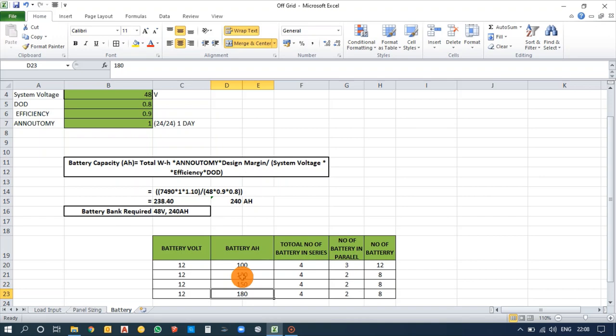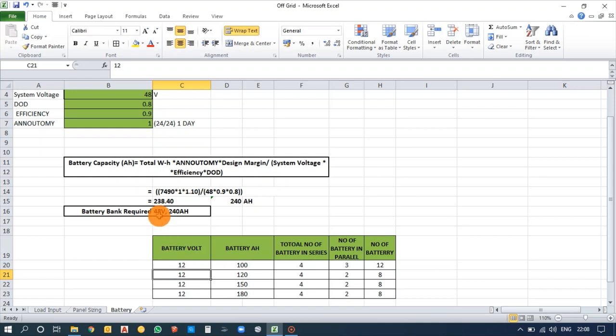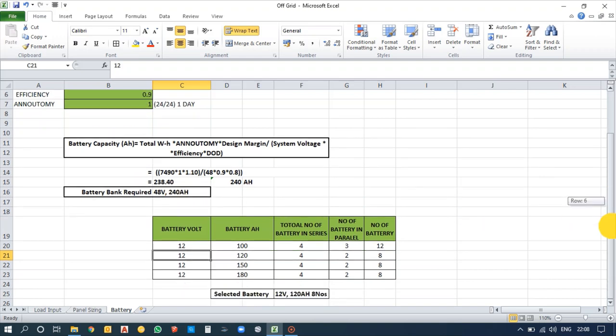I have selected 120 Ah, 12-volt batteries. Four batteries in series give 48 volts, and two sets in parallel give 240 Ah — meeting my battery bank requirement. So the final selection is 8 batteries of 12V, 120 Ah, which is more than enough to achieve the backup need for this system.